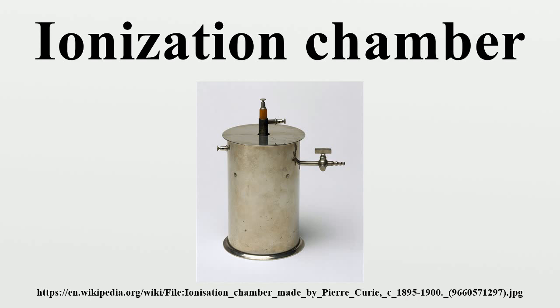This continual generation of charge produces an ionization current, which is a measure of the total ionizing dose entering the chamber. However, the chamber cannot discriminate between radiation types and cannot produce an energy spectrum of radiation. The electric field also enables the device to work continuously by mopping up electrons, which prevents the fill gas from becoming saturated where no more ions could be collected, and by preventing the recombination of ion pairs, which would diminish the ion current.